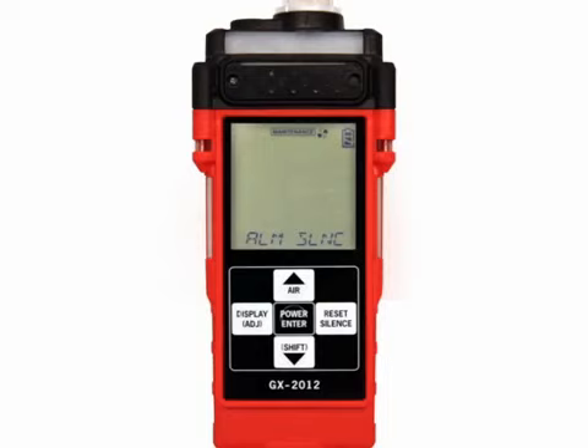With alarm silence set to off, you cannot silence the buzzer. If an alarm condition occurs and you enter display mode, the buzzer will not be silenced and the LEDs will continue to flash. Upon return to measuring mode, if there is still an alarm condition and the alarms are set up as latching, you must wait until it clears before you can press the reset silence button to clear the alarm indications. Use the air or shift buttons to display the alarm silence menu item.